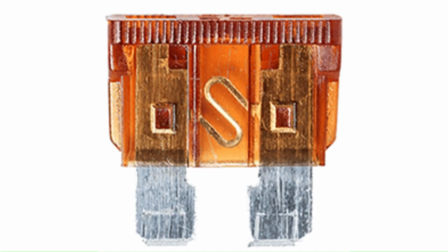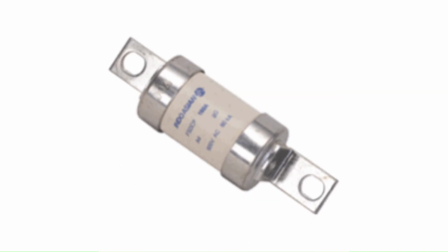In knife blade type switches, the fuse wire is replaced in a live circuit with the help of a fuse puller. The bolted type HRC fuses have two conducting plates which are bolted to the fuse base. This fuse requires an additional circuit for taking out the switch without getting a shock.